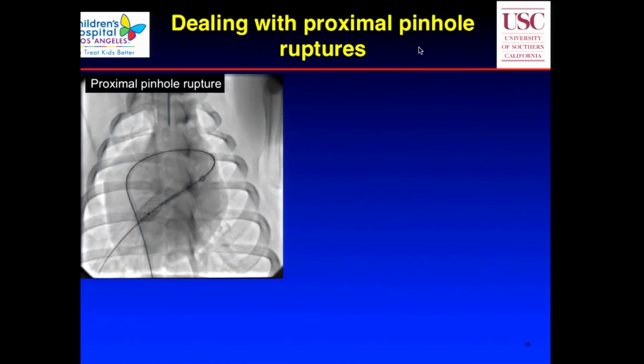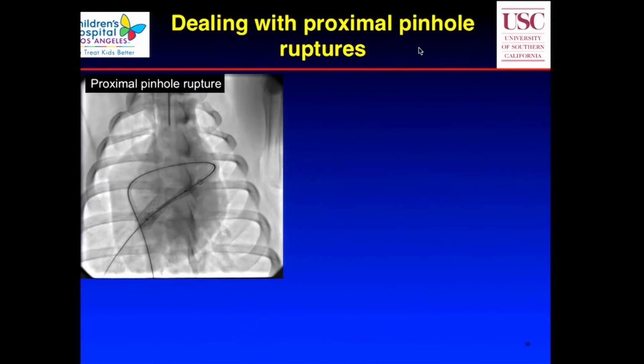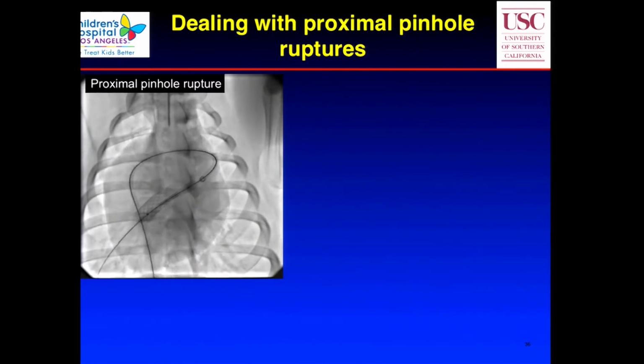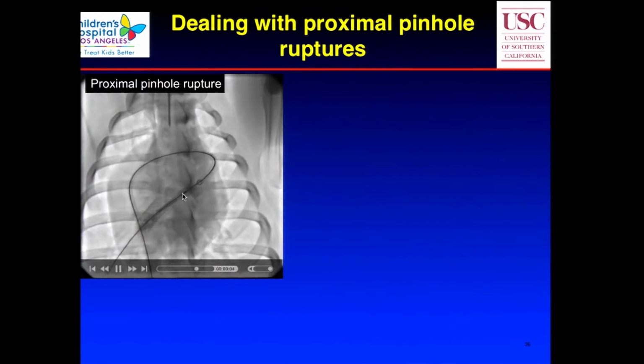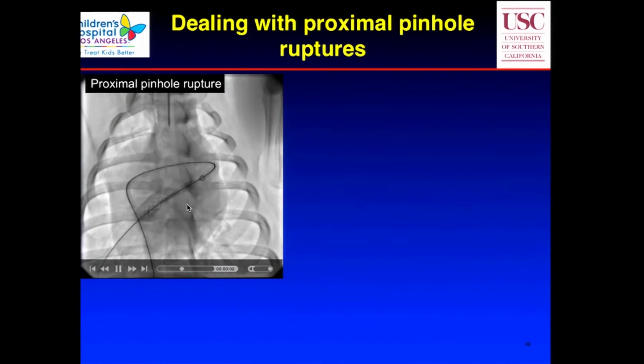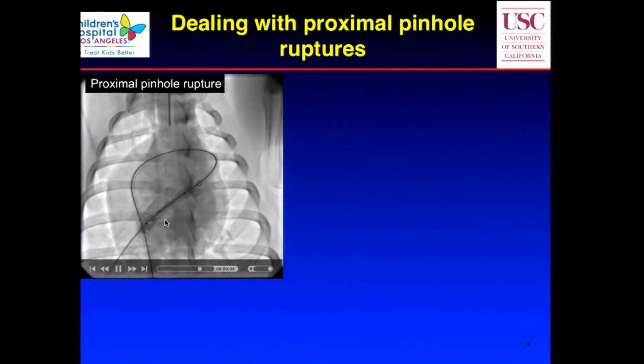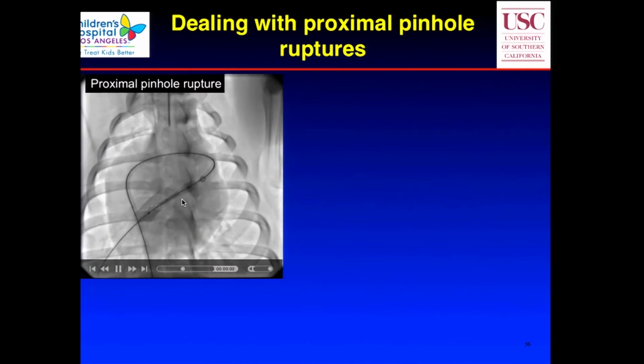Now, this is an example that I did when I was doing a live case demonstration in a pig model in Japan a few years back. I purposely mounted a stent on the balloon, and I purposely stuck some pinholes there just to prove the point. So here we're inflating this, and you notice that as you inflate, the balloon is not inflating very well. In fact, there are some pinholes over here.